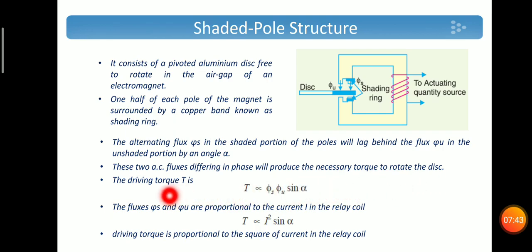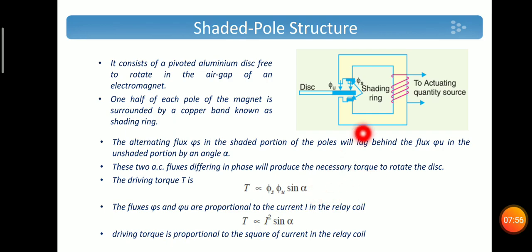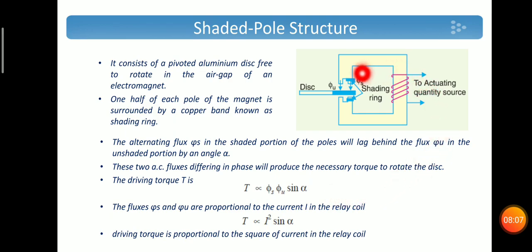The driving torque T is proportional to phi-s · phi-u · sin(α). The fluxes phi-s and phi-u are both proportional to the current I in the relay coil, so the torque is proportional to I² · sin(α). Therefore, the driving torque is proportional to the current squared, and it does not depend on the direction of the current.